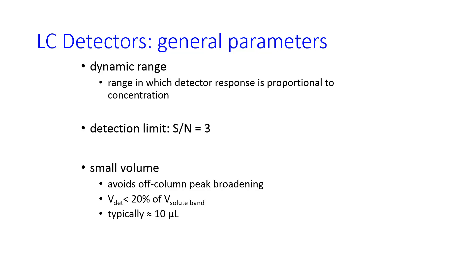Detectors for HPLC. Generally, we want them to have a small volume, and the reason for this is that we have pretty small concentrations that we're using in HPLC. The typical detector volume is about 10 microliters. And we will also want the detector to be pressurized so that when the high-pressure solvent comes into the detector, any dissolved gas stays at high pressure, and it doesn't come out into the gas phase. This would have a big effect, especially on light-based detectors.